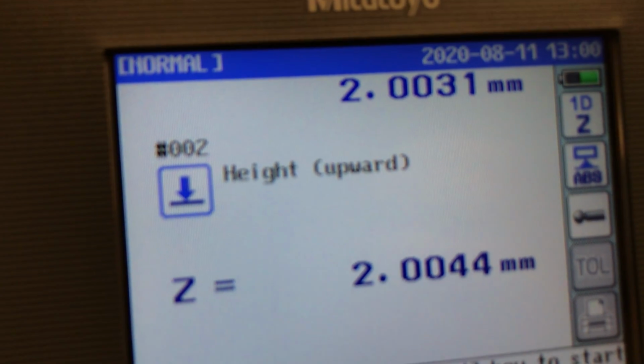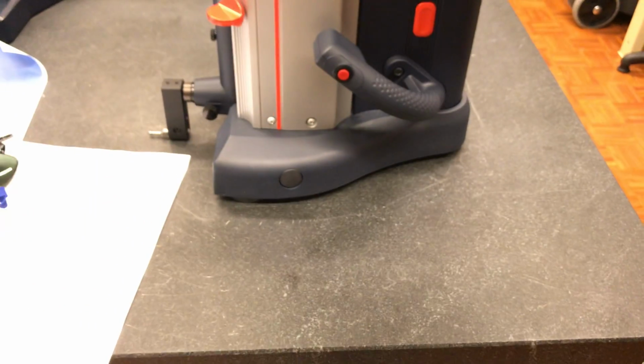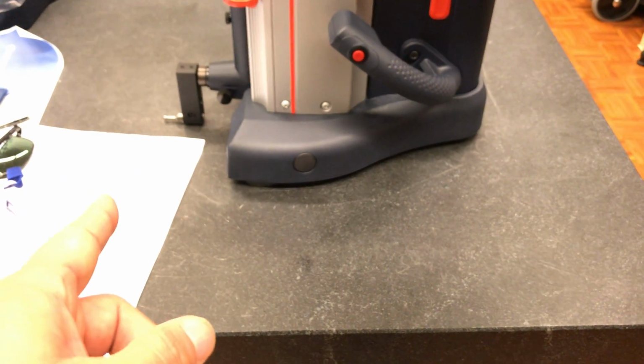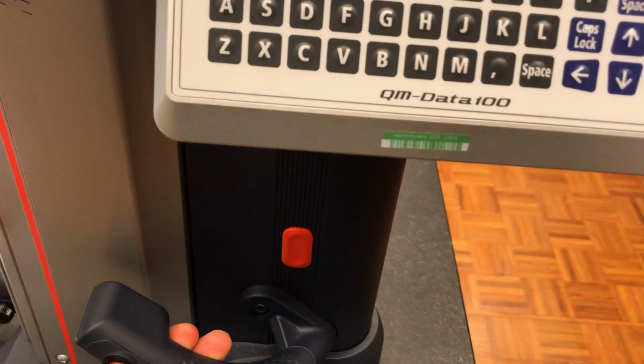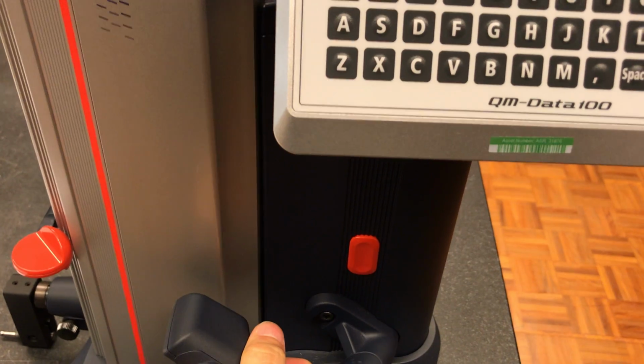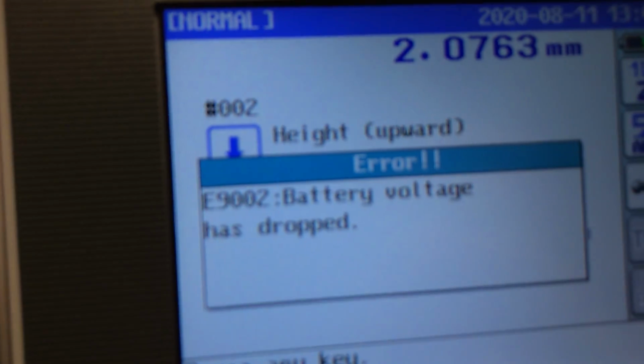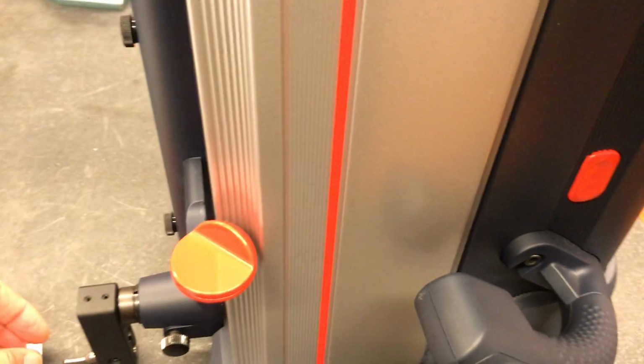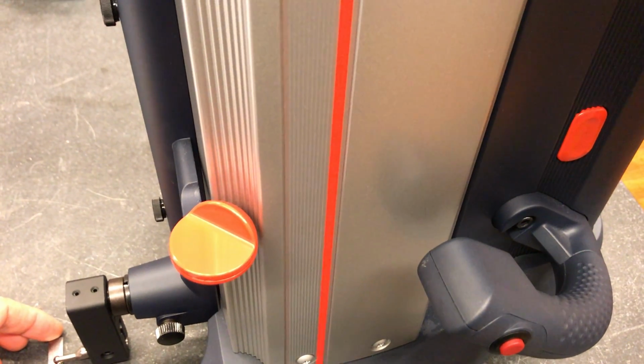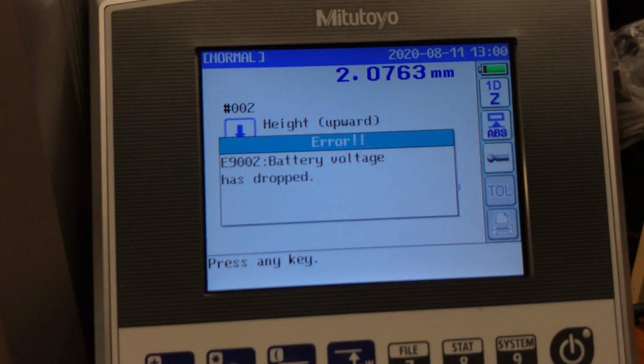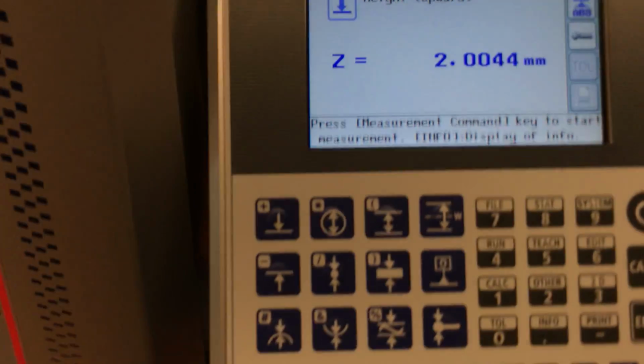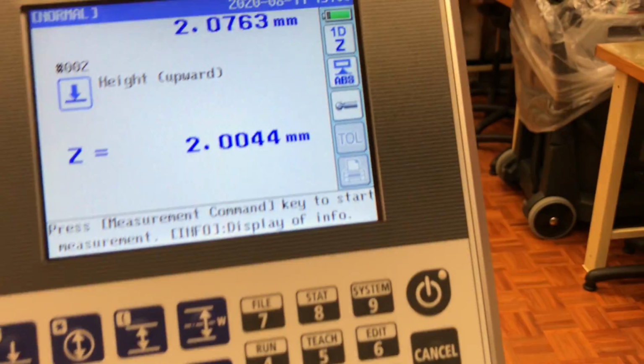Now I'm pressing on the probe downward. So this machine is not 100% accurate. The reason for that may be the table levelness, or maybe some particles in here. So I'm going to try to move the machine to another position. Tell me if the battery dropped, because we use the air cushion, and I'm going to check the height in this position. Hopefully it will make some difference. Just remember that I actually need to calibrate the machine earlier.